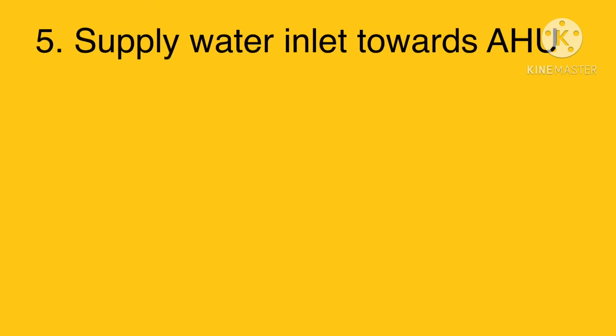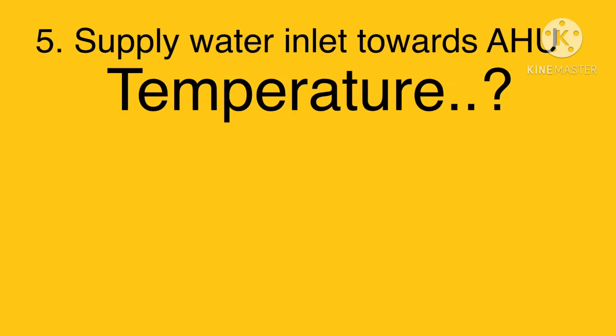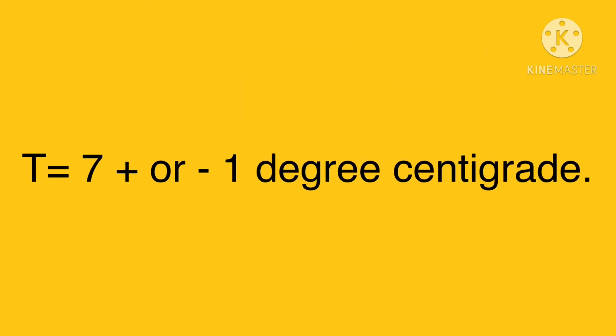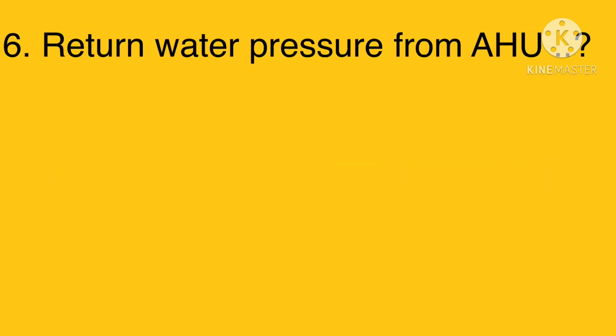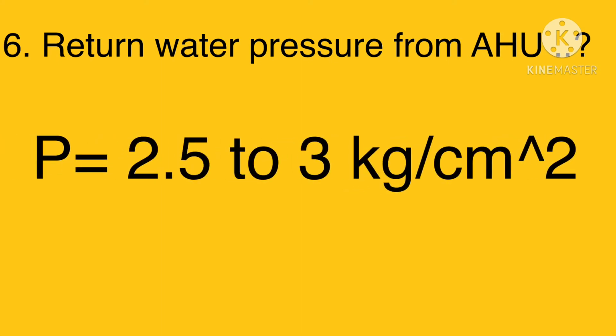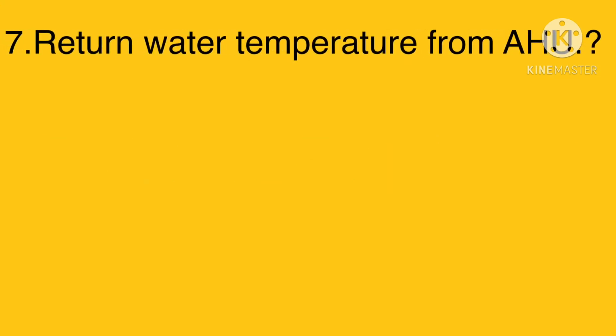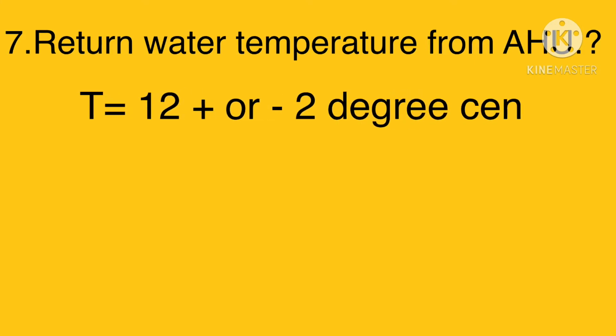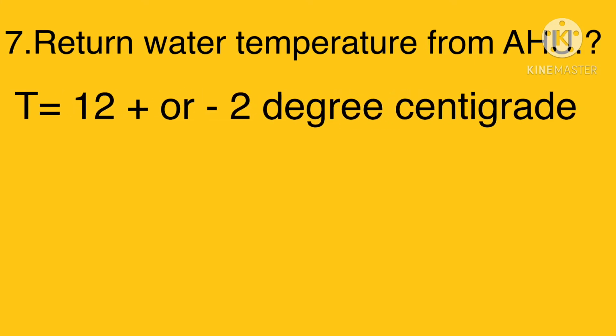What is the temperature from the evaporator outlet towards the AHU inlet supply water? The temperature is 7 degrees centigrade plus or minus 1 degree centigrade. What is the pressure from the AHU outlet towards the evaporator inlet return water? Here the pressure is around 2.5 to 3 kg per centimeter square. What is the temperature of the AHU outlet towards the evaporator inlet return water? Here the temperature is around 12 degrees centigrade plus or minus 2 degrees centigrade.